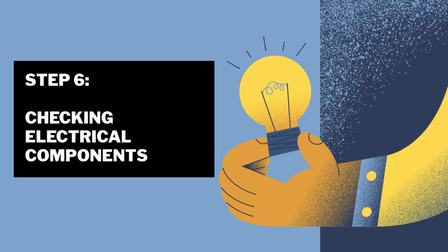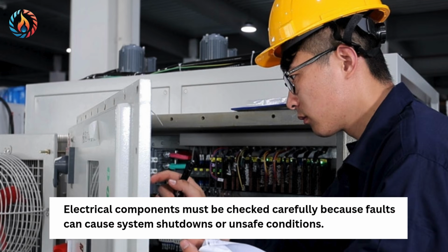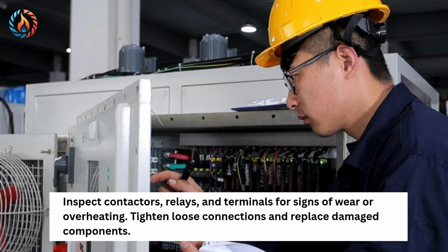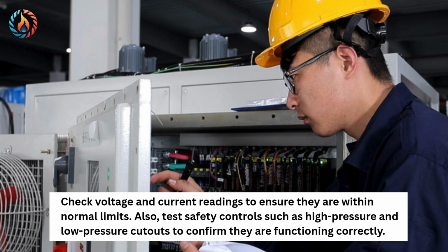Step 6. Checking electrical components. Electrical components must be checked carefully because faults can cause system shutdowns or unsafe conditions. Inspect contactors, relays, and terminals for signs of wear or overheating. Tighten loose connections and replace damaged components. Check voltage and current readings to ensure they are within normal limits. Also, test safety controls such as high-pressure and low-pressure cutouts to confirm they are functioning correctly.